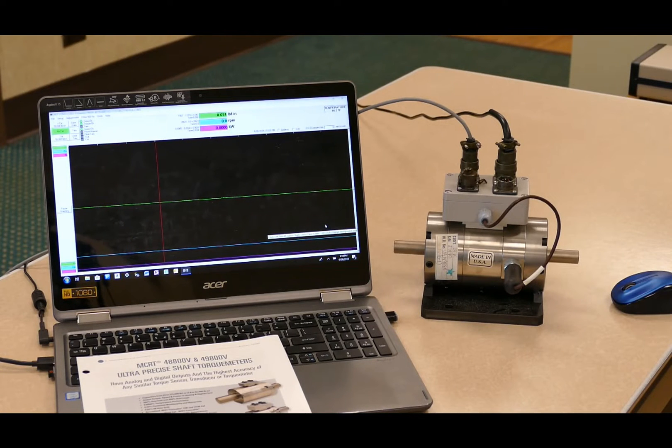They're also available with different mechanical overload ratings. Available mechanical overload ratings are 200%, 400%, and even 1000%, which offers supreme protection against torsional spikes or peaks that may be seen in different types of applications, either with high starting torques or applications where you have large torsional spikes such as diesel engine testing.